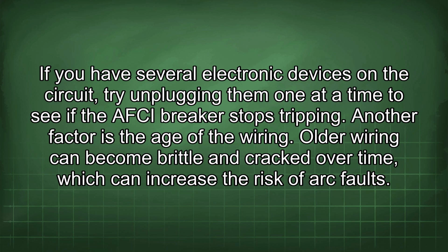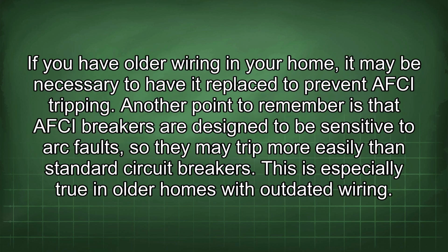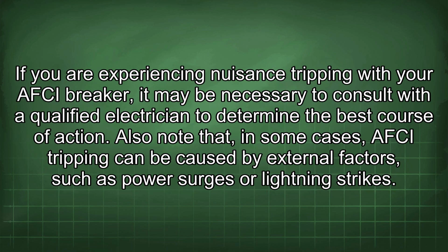Older wiring can become brittle and cracked over time, which can increase the risk of arc faults. If you have older wiring in your home, it may be necessary to have it replaced to prevent AFCI tripping. Another point to remember is that AFCI breakers are designed to be sensitive to arc faults, so they may trip more easily than standard circuit breakers. This is especially true in older homes with outdated wiring. If you are experiencing nuisance tripping with your AFCI breaker, it may be necessary to consult with a qualified electrician to determine the best course of action.